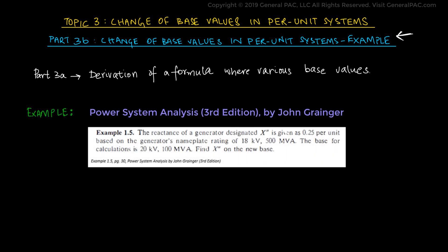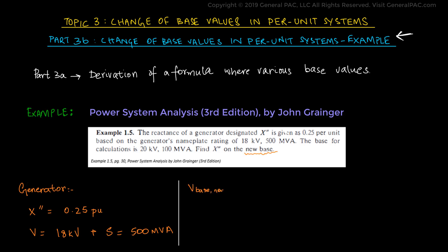This is Example 1.5 from page 30 of Power System Analysis by John Grainger, 3rd edition. In this example, the reactance of the generator is given as X double prime is equal to 0.25 per unit. The rating of the generator is specified as V equals 18 kV and S equals 500 MVA. The problem asks us to find the reactance of the generator in per unit according to the new base values: V base new equals 20 kV and S base new equals 100 MVA.